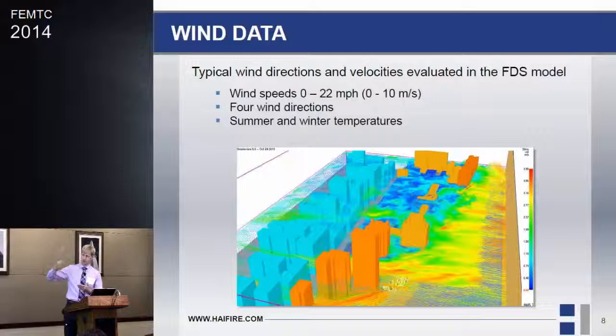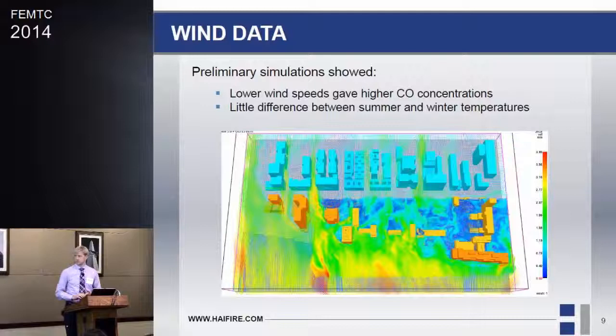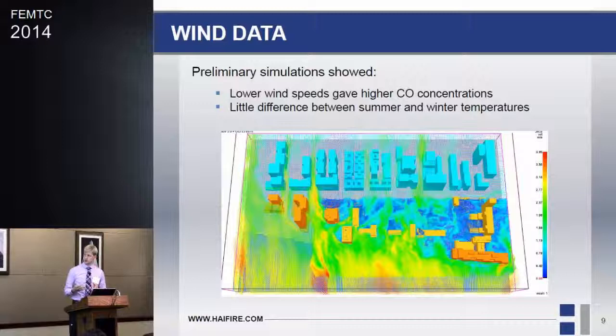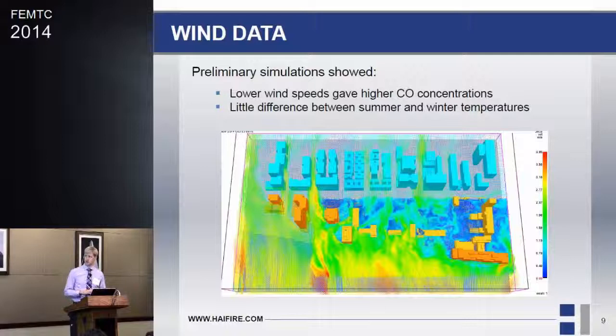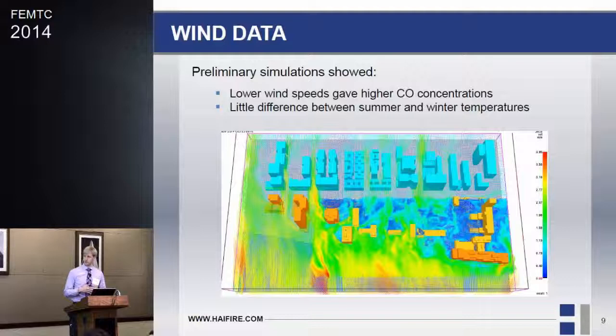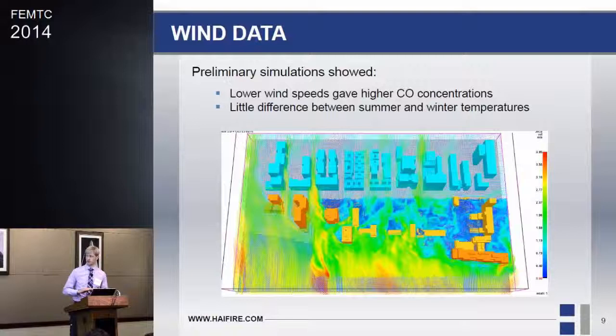We settled on about four major wind directions. You can see wind coming in from the east blowing straight into the opening, with wakes around the buildings and areas of high and low velocities. We also looked at wind from the other side creating a vortex over the river. The preliminary scoping runs showed that lower wind speeds resulted in generally higher concentrations inside the roadway — which makes sense, since high wind velocity just pushes the exhaust out, while low velocity can create pockets of buildup.